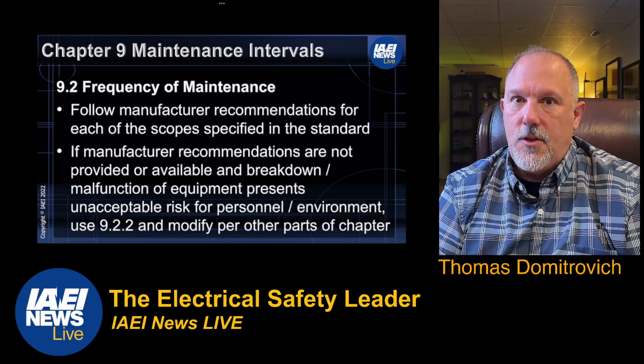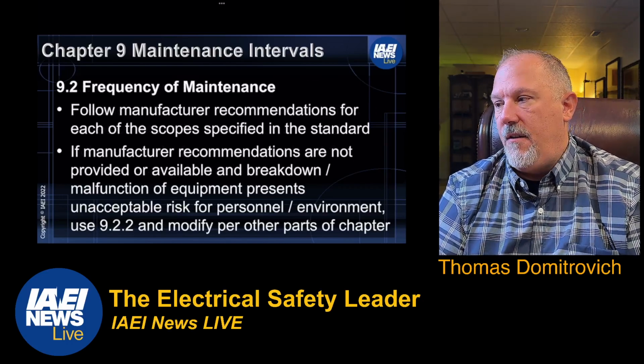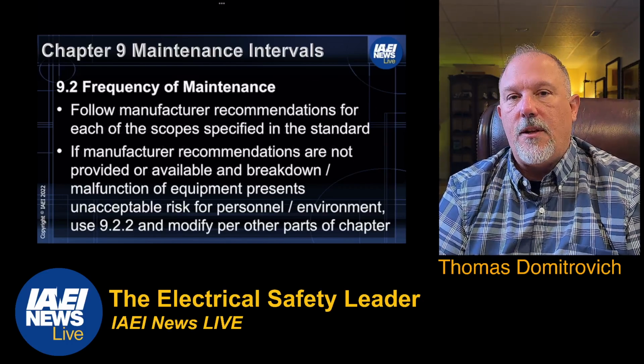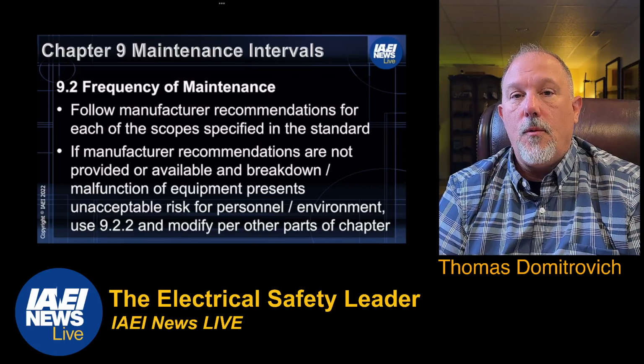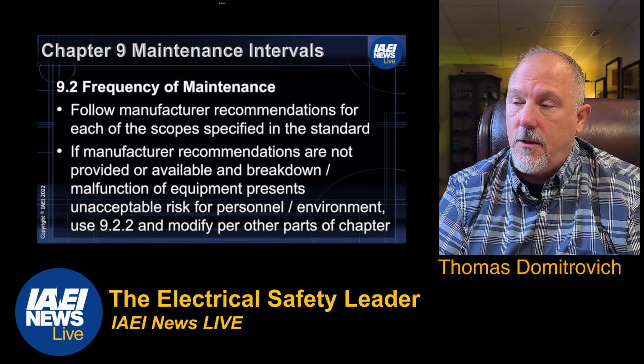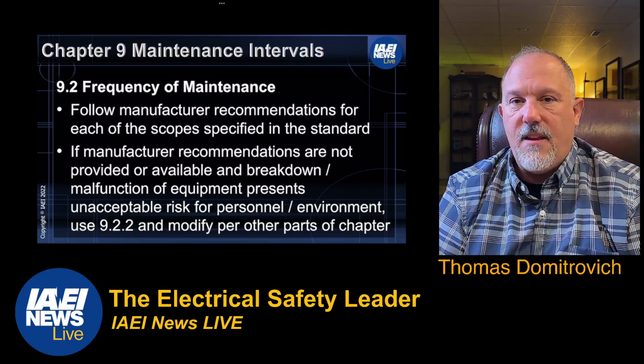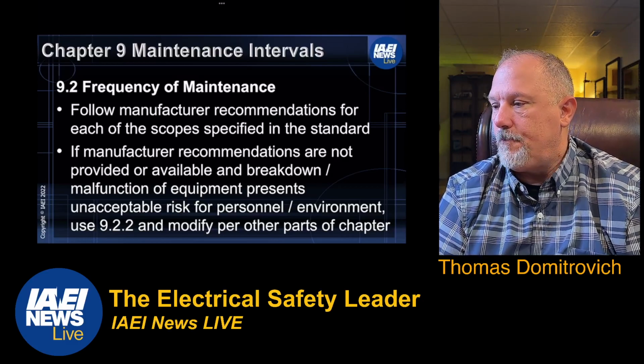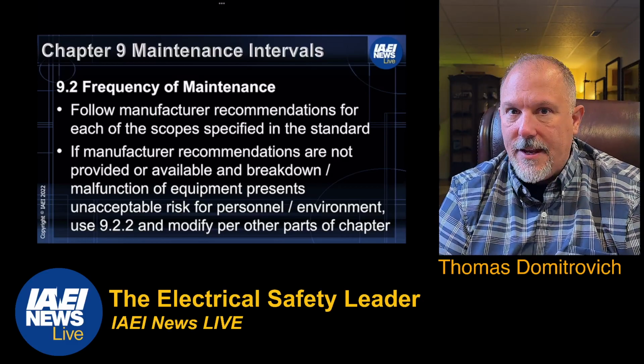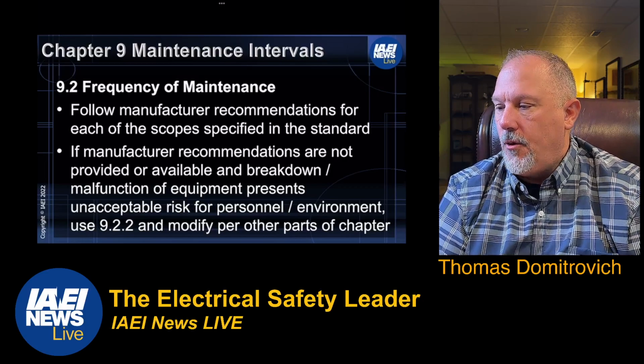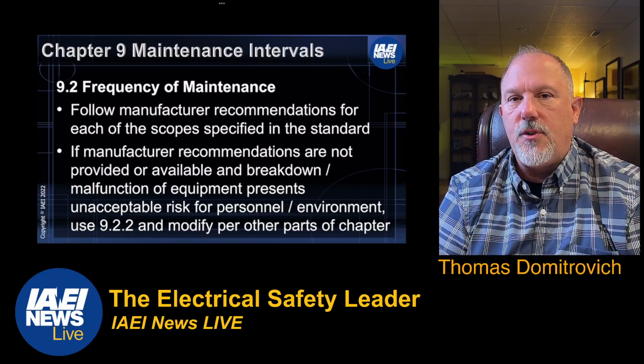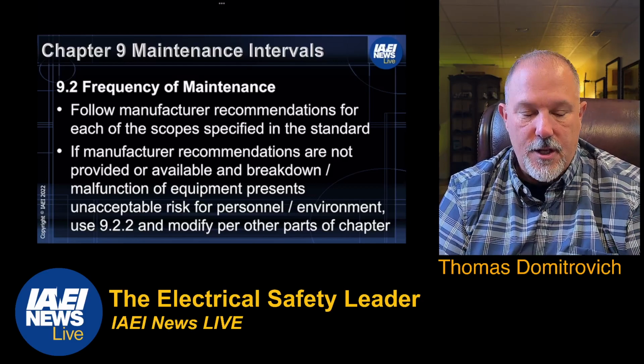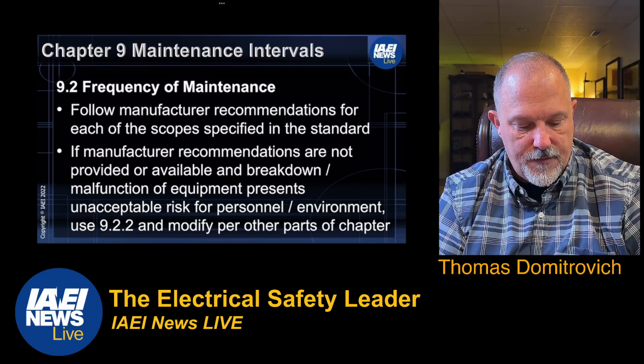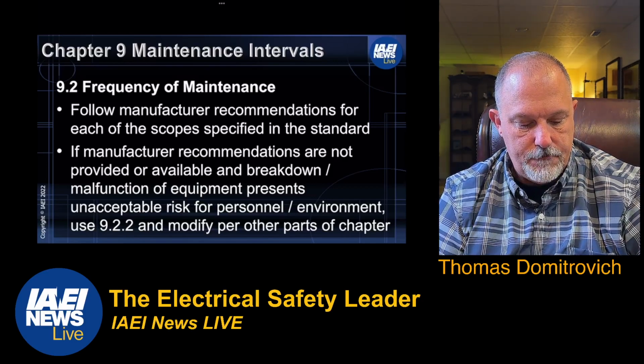Now, 9.2 is where the meat of the frequency of maintenance comes from. Remember, the first thing we tell you to do is go back to the manufacturer and look at their recommendations. If they're not provided, you can use table 9.2.2 to establish those conditions of maintenance.